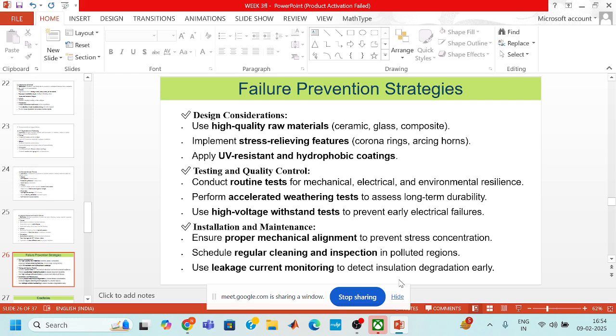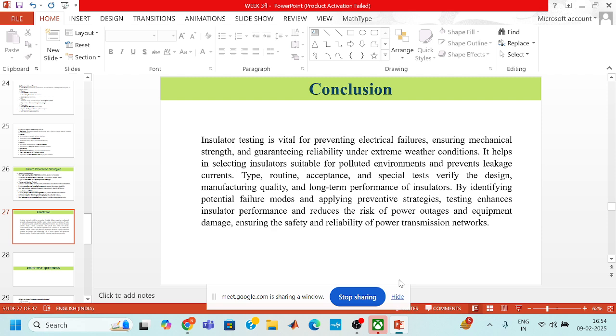Third is installation and maintenance. We have to ensure proper mechanical alignment to prevent stress concentration, schedule regular cleaning and inspection in polluted regions, and use leakage current monitoring to detect insulation degradation early. So in this presentation, as we know, insulator testing is very important for preventing electrical failures. It ensures mechanical strength, guaranteeing reliability under extreme weather conditions. It helps in selecting insulators suitable for polluted environments and prevents leakage currents.